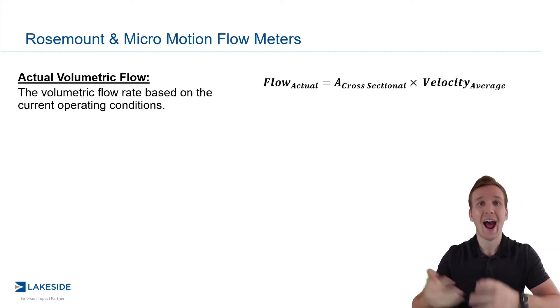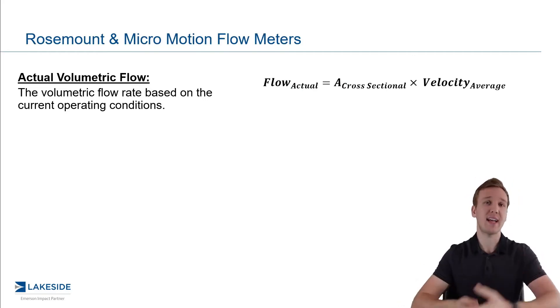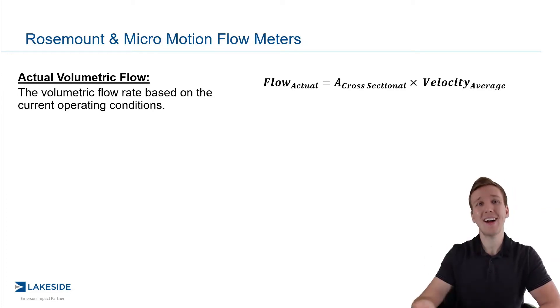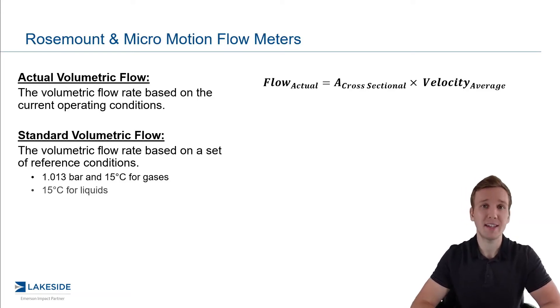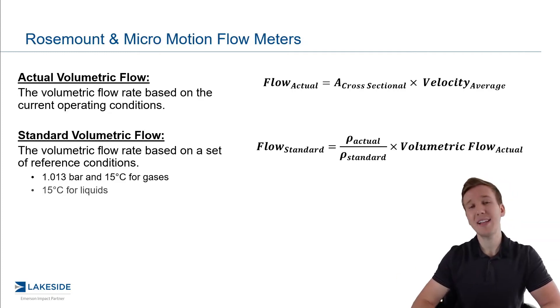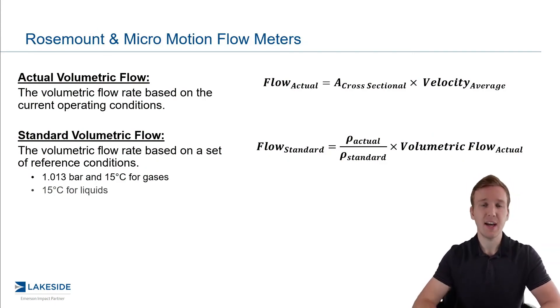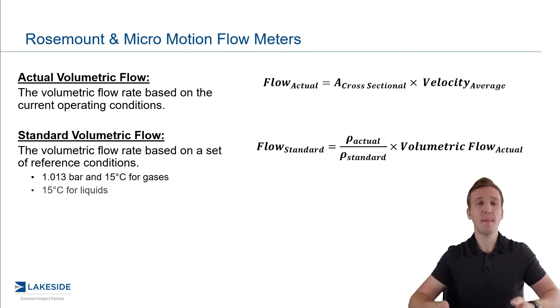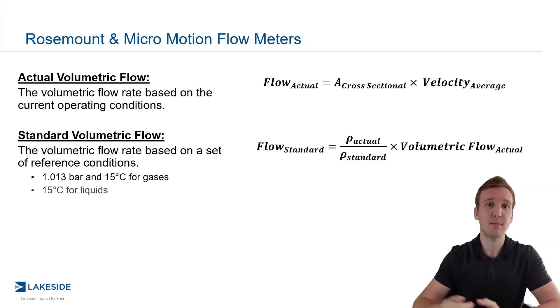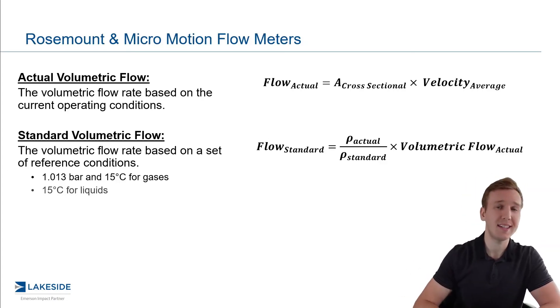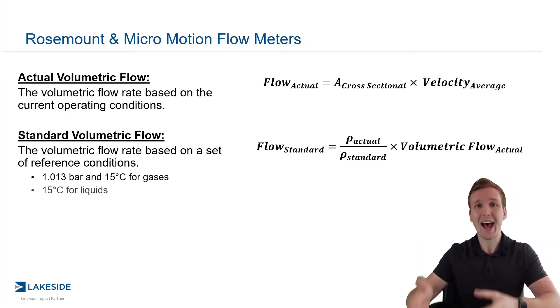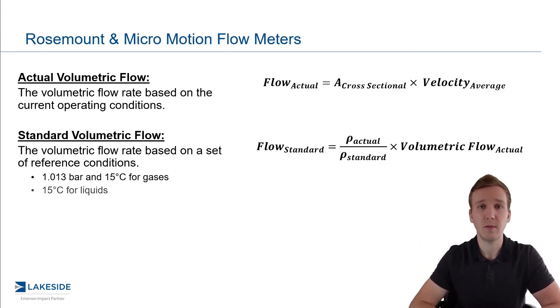If we look at an actual volumetric flow rate, this is just going to be a representation of the average velocity of that fluid in that given cross-sectional area. A way we can standardize this to account for deviations as pressures and temperature change is by referencing some sort of base set of reference conditions — most commonly one bar and 15 degrees Celsius in Canada. We would take that actual volumetric flow rate and multiply it by the ratio of the actual density over the standardized density to get a standardized volumetric flow rate. Keep in mind, this is not compensating for changes in pressures and temperatures — any error due to changes in density will still occur — but this allows us to add these standardized volumes over time, which is very important for totalizations.